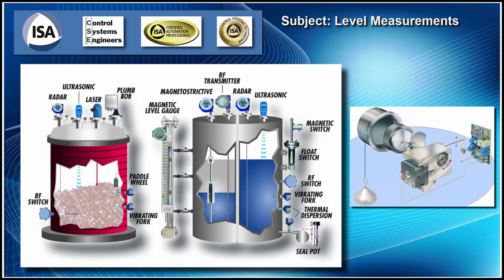Now, notice at the bottom how the hook just kind of hooks on the cable. Sometimes you use a chain. But the problem is, if you're doing this in a tank that has a volatile fluid and there's a lot of vapor, you need to put a jumper between the cable and the actual metal float, the bob, because it can jerk. And as you fill up these tanks, you get a separation of charge.